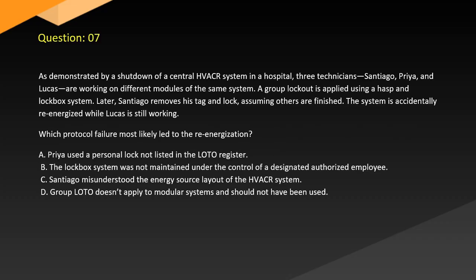Question 7. Consider a shutdown of a central HVACR system in a hospital. Three technicians, Santiago, Priya, and Lucas, are working on different modules of the same system. Group lockout is applied using a hasp and lockbox system. Later, Santiago removes his tag and lock, assuming others are finished. The system is accidentally re-energized while Lucas is still working. Which protocol failure most likely led to the re-energization?